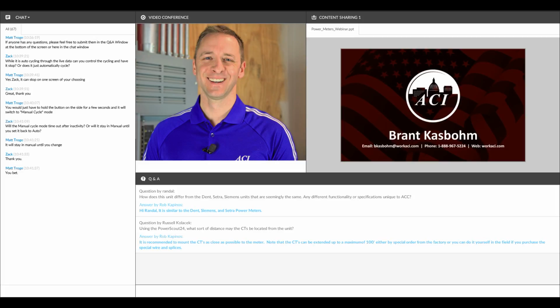Another question is, what's the difference between the revenue grade CTs and the non-revenue grade CTs? That's simply that the revenue grade CTs are manufactured to a higher level of tolerance and accuracy. So they're designed to meet the highest level of revenue grade accuracy, which is 0.2%. The standard CTs, in order to keep costs down, don't always meet that specification. So the revenue grade ones, when ordered, can be specified as such, and those can be used to meet the highest level of revenue grade accuracies throughout North America.